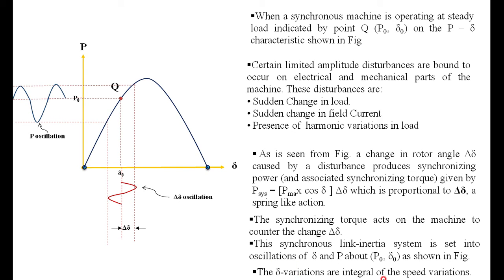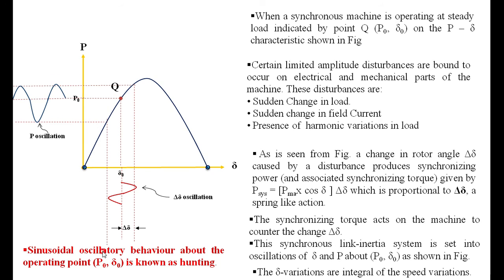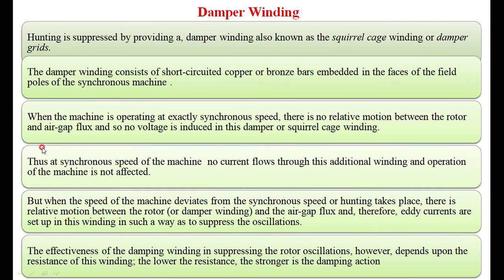The delta variations are an integral part of the speed variation. The oscillatory behavior about the operating point P₀ and delta₀ is known as hunting within the synchronous machine. These oscillations or hunting can be suppressed by damper windings placed on the faces of the rotor. The damper winding is an extra winding placed on the rotor faces, also called squirrel cage winding or damper grids. It consists of short-circuited copper bars embedded in the faces of the field poles of the synchronous machine.